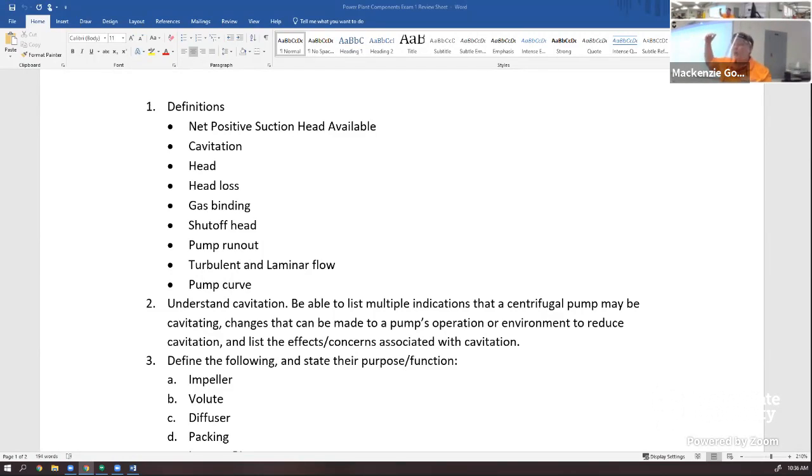So what they're saying is we've got cavitation, right? Which is when we have essentially low pressure that allows void bubbles to form in our fluid. And then when those collapse, that explosion in the fluid causes cavitation in our pump, right? And damage our pump. So in order to avoid that pressure creating that level of vacuum, you're going to have your net positive suction head required, right? So that's going to be how much suction you have to put through the pump to ensure that that low pressure doesn't form on the entrance to it, right?